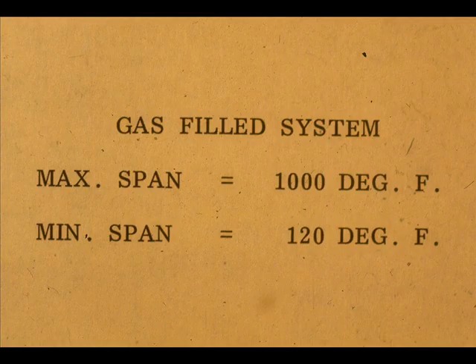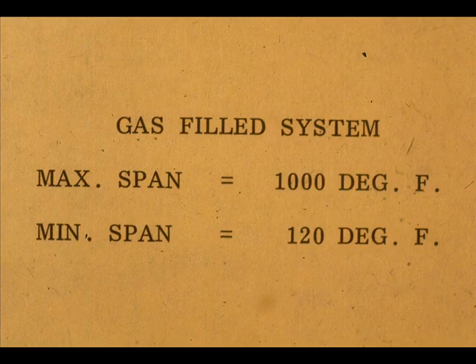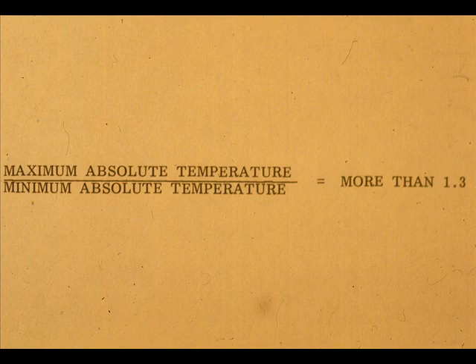They have a maximum operating span of 1,000 degrees Fahrenheit and a minimum span of about 120 degrees Fahrenheit. The span of the instrument is determined by the range chosen. Remember, we use absolute values. The ratio of the maximum absolute temperature to the minimum absolute temperature must be more than 1.3.